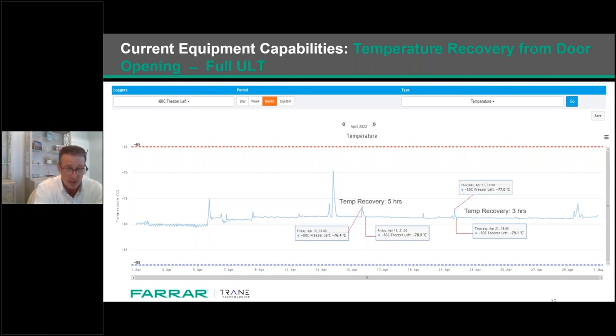So on the system, since the refrigeration system should never operate continuously, you should probably have someone look at the system if you ever see a flat line. So temperature recovery from door opening is one of the major issues. It was one of your major concerns from the poll. And keep in mind, the data shown in this slide depicts a minus 80 freezer fully loaded with products. So it's not an empty freezer, it's a fully loaded freezer. Next slide, please.